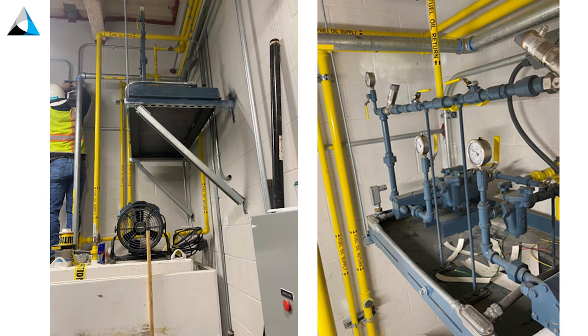These return pumps were supposed to be mounted to the day tank in the generator room, but when we showed up on site they were not. Apparently they had come on a skid, and the contractor — being very proud of his ingenuity and resourcefulness — mounted them way up high on the wall where you can't access them. So that's a maintenance issue we noted.